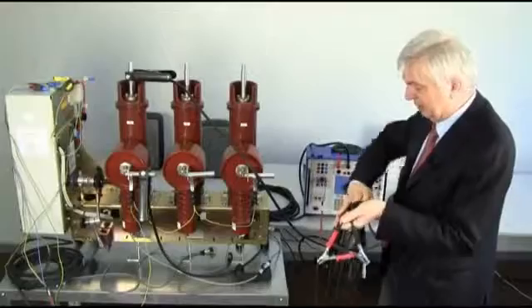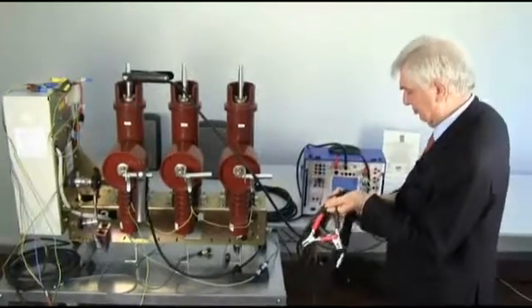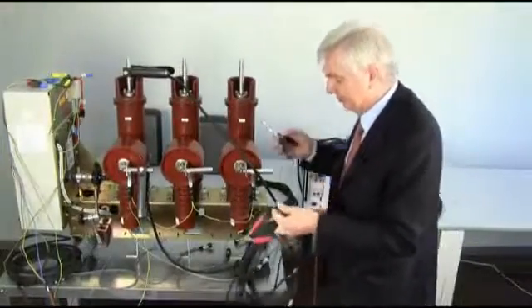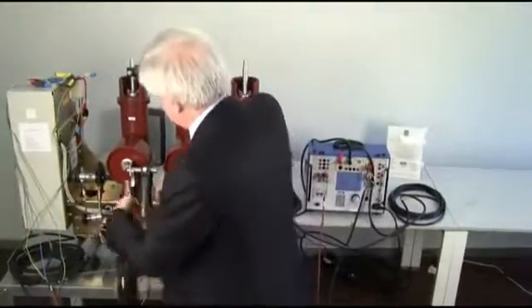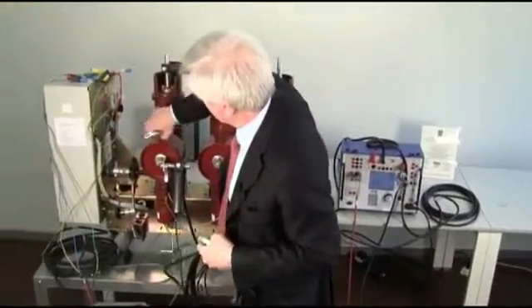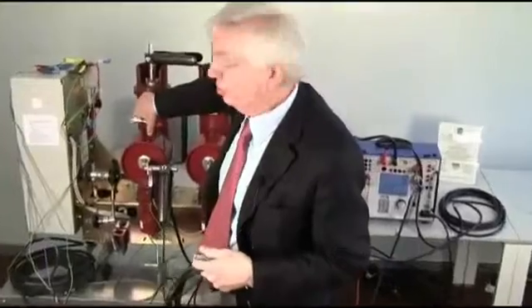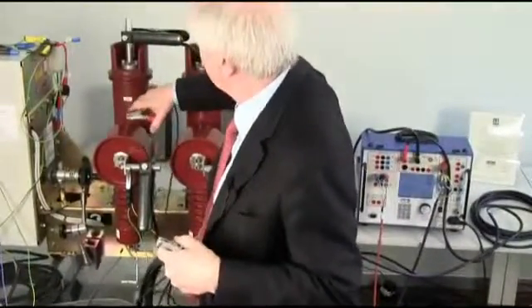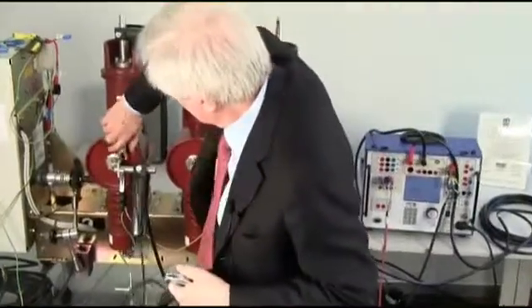And the cable goes to this connector here. So the idea is that you should get as close as possible to the contact itself, because otherwise all the drops that you may have in between is measured as contact resistance.